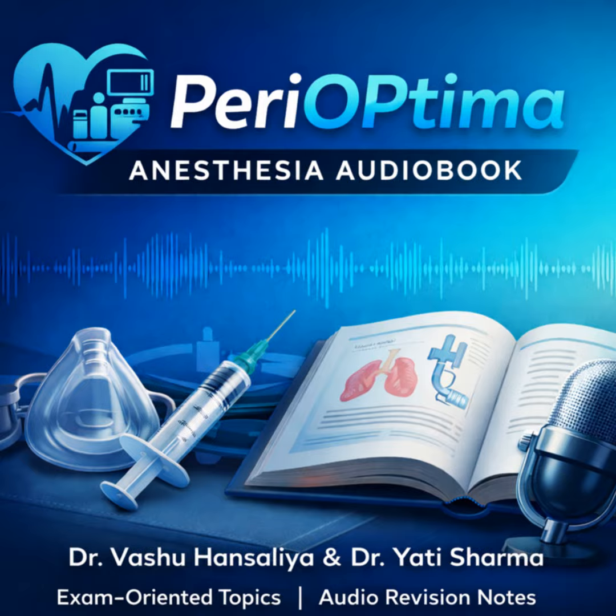You should know the basic chemical reaction. CO2 plus water gives you carbonic acid, which then reacts with the calcium hydroxide to form calcium carbonate and more water. And there's an indicator dye in there as well? Yes, usually ethyl violet, which changes color typically from white to purple when the granules are exhausted and the pH drops. Okay, number 4. Number 4, the reservoir bag.